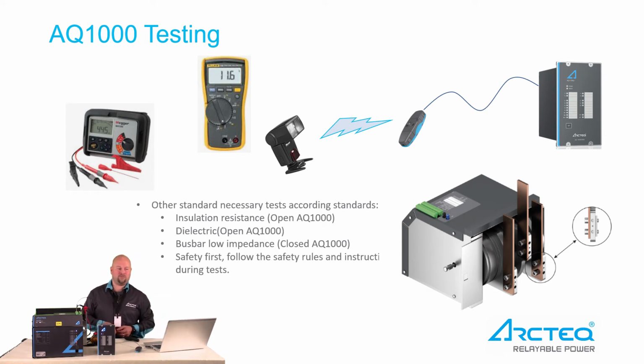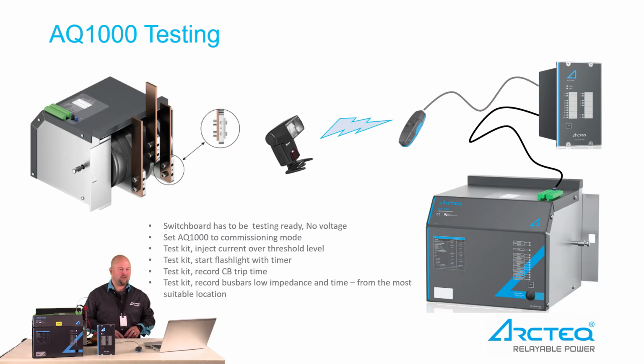Safety first. Follow the safety rules, standards, instructions during the test. Always safety first. And many times, the switchboard has to be testing ready, no voltage. When we are closing this, it will make the short circuit. So if there's voltage on the board, this can handle the voltage, but it is not the purpose. The purpose is that the switchboard is of course testing ready.